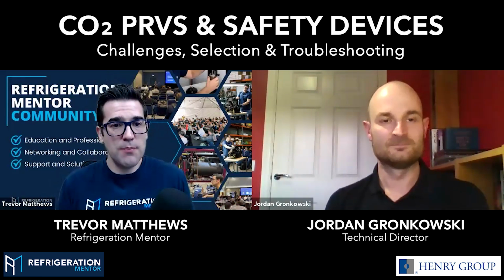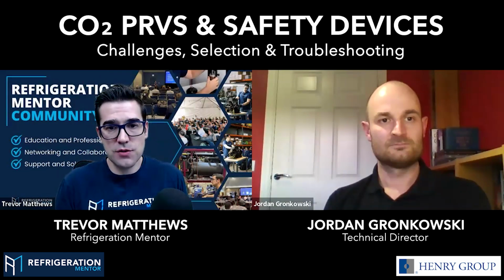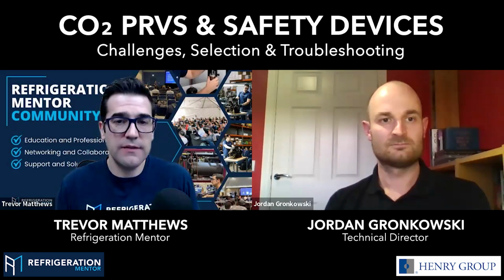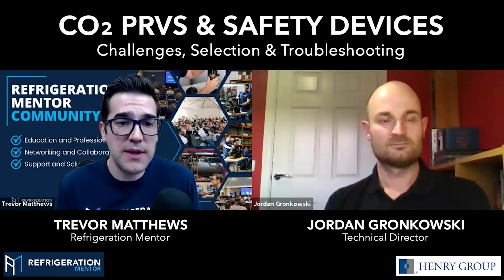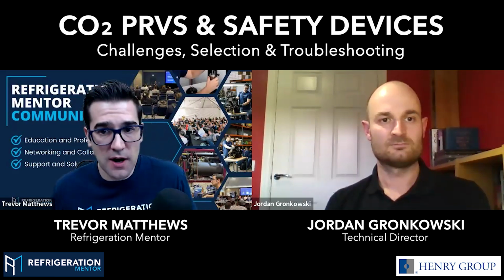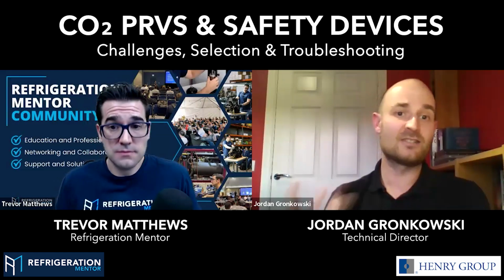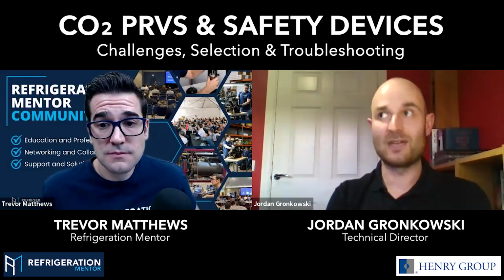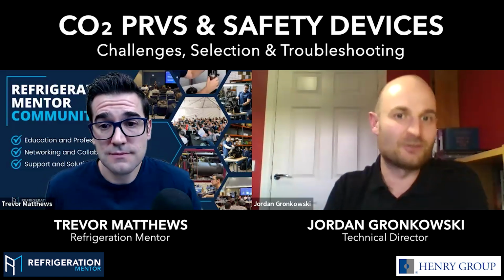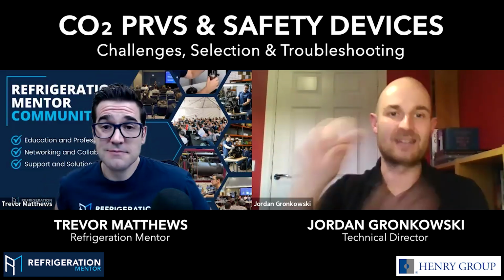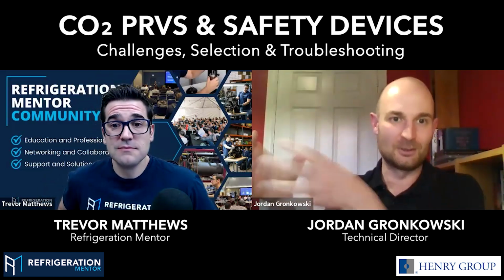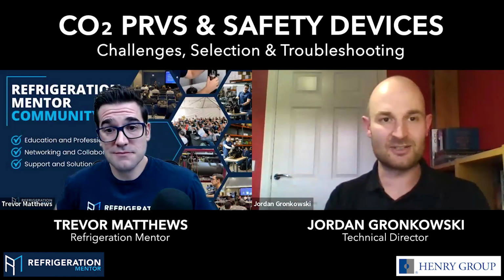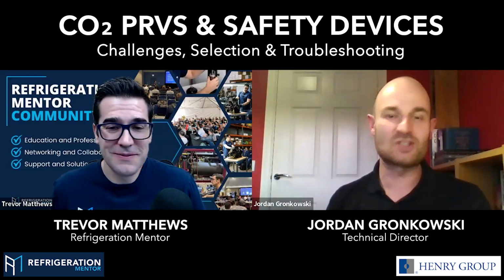Yeah, that's a great point. So 90% if you're doing that. Once again, if it's 100 bar or 1400 PSI, you'd go up to 90 bar, correct? So that's the max you want to do. And again, you're looking for a leak as per the manufacturer's definition of leak tightness. For us, it's that tube into a bottle and you're looking for 0 bubbles. Different manufacturers will have different definitions and requirements.